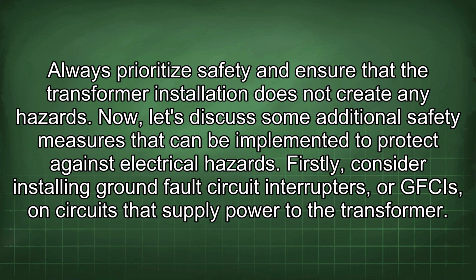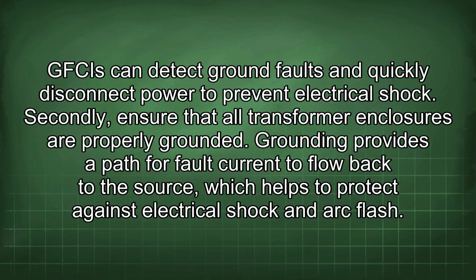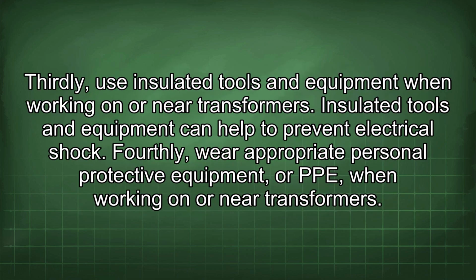Now, let's discuss some additional safety measures that can be implemented to protect against electrical hazards. Firstly, consider installing ground fault circuit interrupters, or GFCIs, on circuits that supply power to the transformer. GFCIs can detect ground faults and quickly disconnect power to prevent electrical shock. Secondly, ensure that all transformer enclosures are properly grounded. Grounding provides a path for fault current to flow back to the source, which helps to protect against electrical shock and arc flash. Thirdly, use insulated tools and equipment when working on or near transformers.